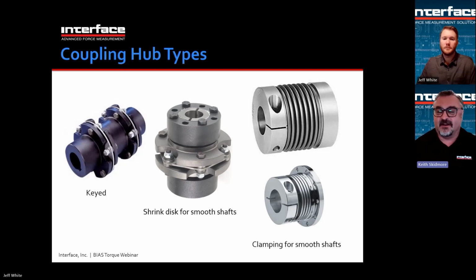So it would be a line fit, where it slides together without a lot of slop, and then it can grip down as you tighten the hub. The reason for that is this is steel, so imagine it doesn't deflect all that much. So you need very tight clearance before you start gripping. Otherwise, it doesn't deflect enough to get a good grip.